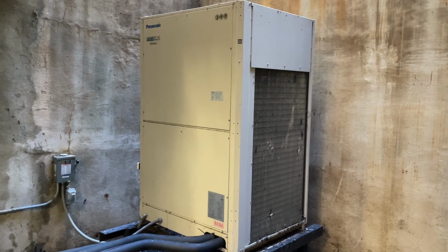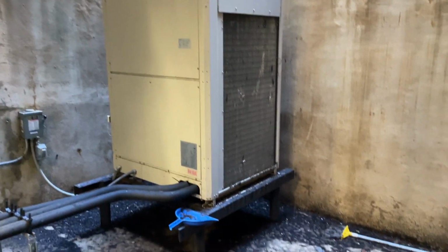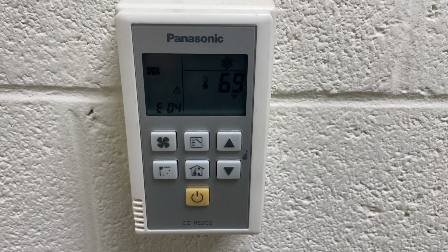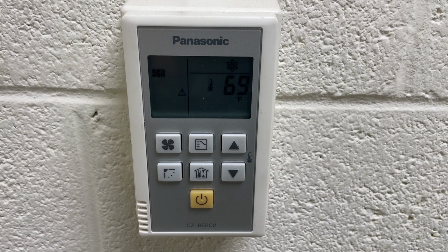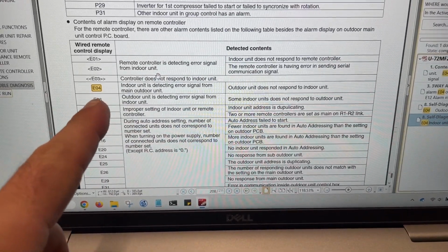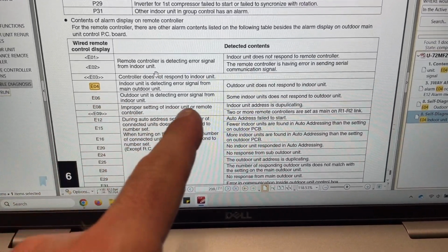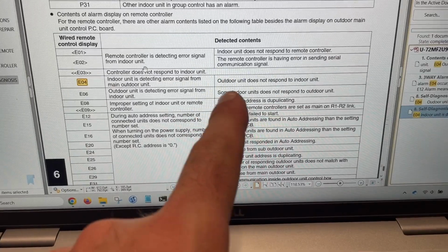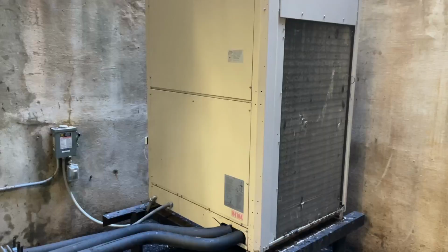Got a Panasonic system here that's got an E04 code. It's under this walkway, and here's the error code flashing on the wired remote. An E04 means the indoor unit doesn't see a response from the outdoor unit.